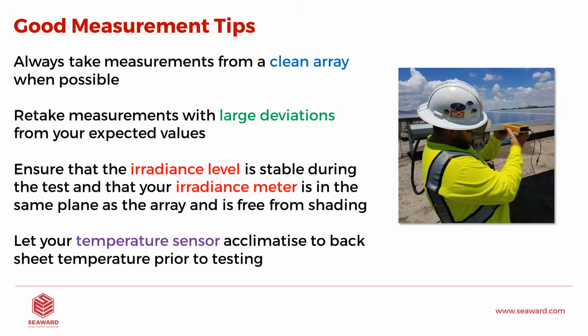I'm not just going to save that and give it to the guy in the office. I'm going to try and prove a negative. Okay, I'm going to try and prove that negative result. So if you see a large deviation from your expected values, test it again, test it again, test it again. And if you can repeat that large deviation, that confirms to you that there is actually a problem with the string and it wasn't just something errant in the test.